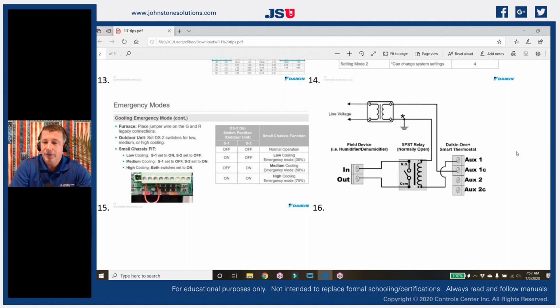Well, if it all runs on temperature sensors and pressure transducers, what is it really using a thermostat for anyhow? The only thing it's doing is just saying, hey, this is where we should or should not be running, right? So we could simply lock these things into emergency mode if we need to. If we have some kind of a communication issue from our thermostat to our indoor unit, bad thermostat, whatever, we can actually put these into an emergency mode so it will just run on its own.